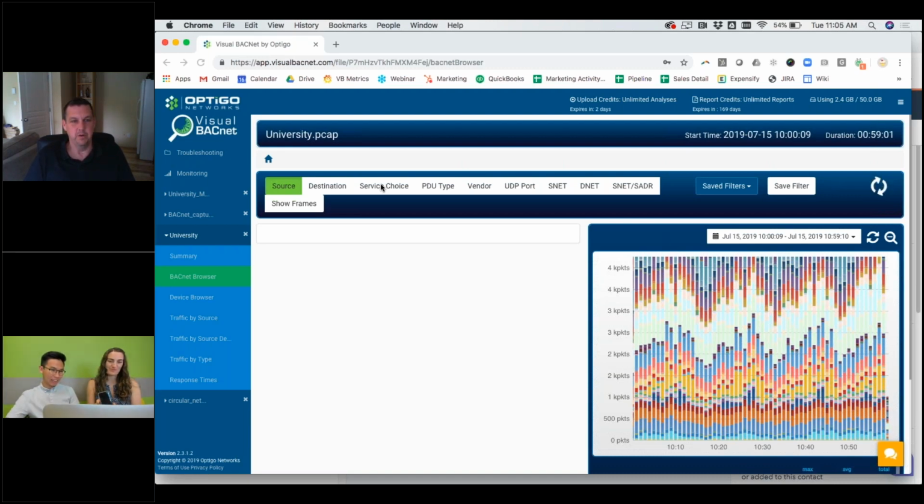So if there's that many who-has requests, Chris, there's probably a lot of devices that aren't being updated on the information. So something's not working correctly, or nothing's under actual control, and so your site's not being directly affected. Okay. So in this case, I would say scenarios like this can be a little bit overwhelming: what do I do to get rid of all of these?